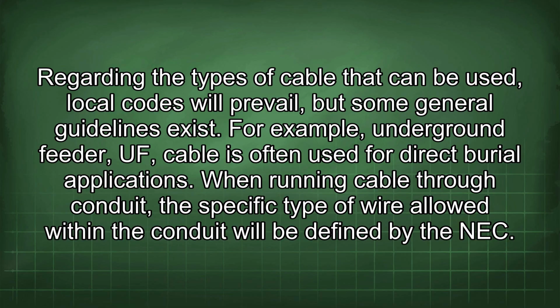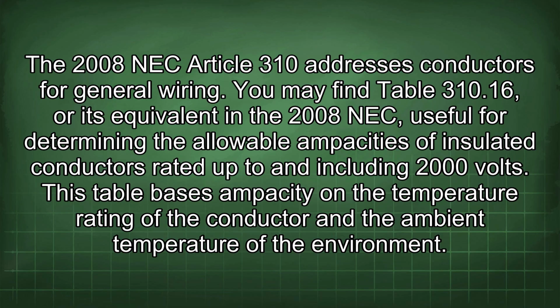Regarding the types of cable that can be used, local codes will prevail, but some general guidelines exist. For example, underground feeder cable is often used for direct burial applications. When running cable through conduit, the specific type of wire allowed within the conduit will be defined by the NEC. The 2008 NEC Article 310 addresses conductors for general wiring. You may find Table 310.16 or its equivalent in the 2008 NEC useful for determining the allowable ampacities of insulated conductors rated up to and including 2000 volts.